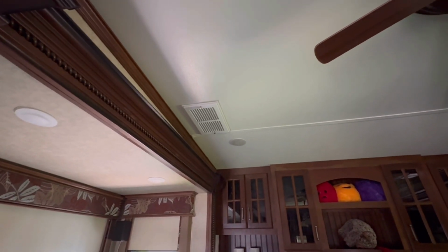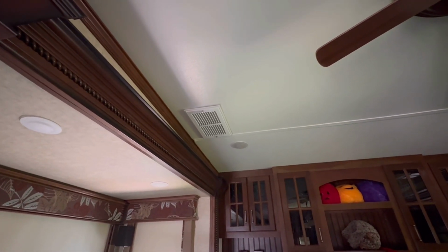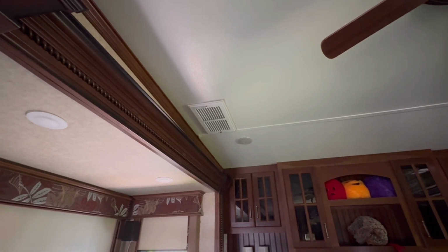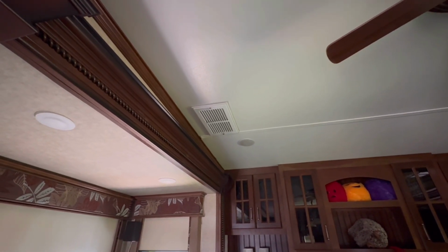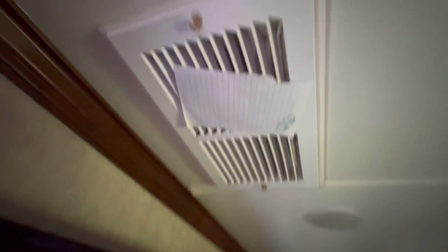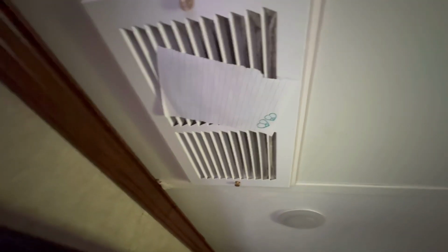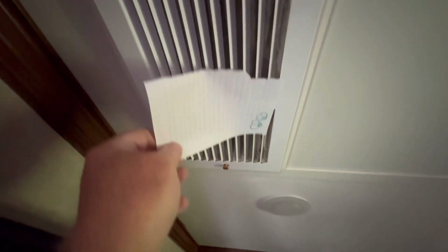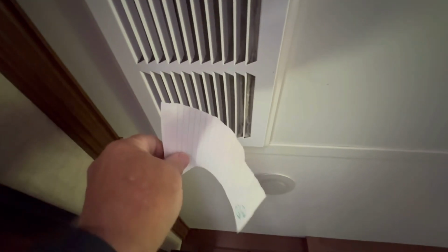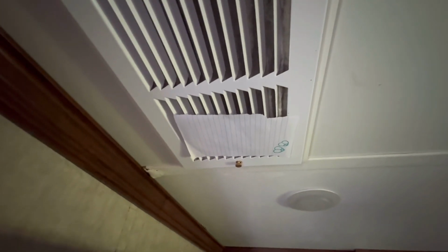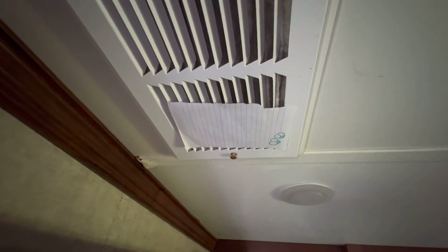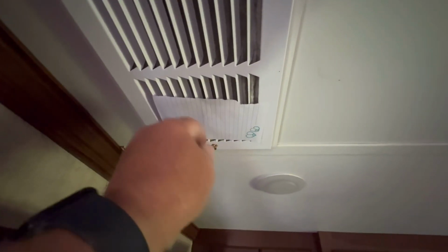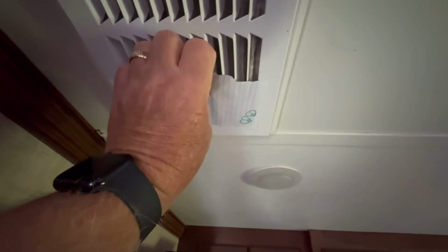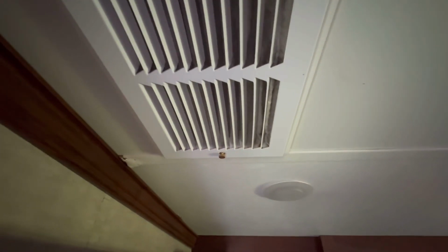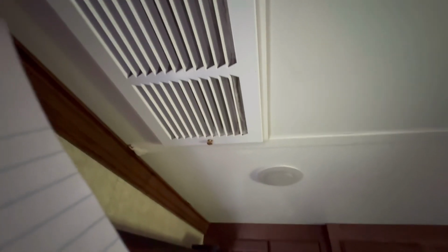So what I'm going to do is put a piece of paper right up next to that return grill, and what I expect to see is that there's suction there that will draw that paper right to it. And here you can see the piece of paper being held right up to the return duct, and we'll take it off so that you can see I'm not taping it or anything. And then we're just going to put it right up there, and you noticed how the pull suction from the air conditioning unit fan pulled that piece of paper right up there. So that tells me that overall this side of the duct is good, it's not collapsed, and we'll go to the other side and do the same check.